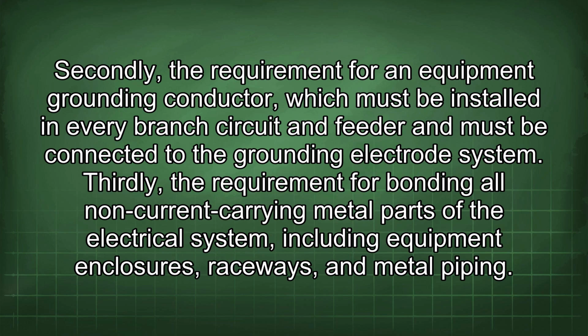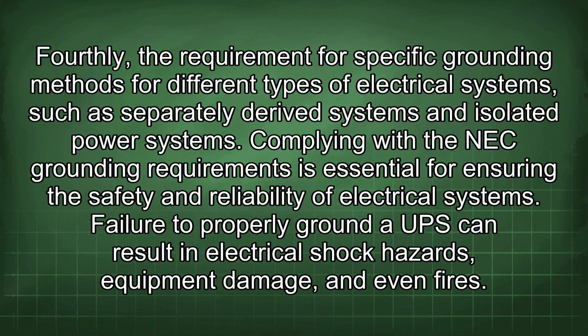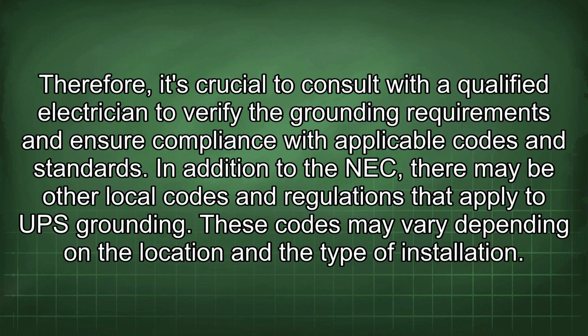Thirdly, the requirement for bonding all non-current carrying metal parts of the electrical system, including equipment enclosures, raceways, and metal piping. Fourthly, the requirement for specific grounding methods for different types of electrical systems, such as separately derived systems and isolated power systems. Complying with the NEC grounding requirements is essential for ensuring the safety and reliability of electrical systems. Failure to properly ground a UPS can result in electrical shock hazards, equipment damage, and even fires. Therefore, it's crucial to consult with a qualified electrician to verify the grounding requirements and ensure compliance with applicable codes and standards.